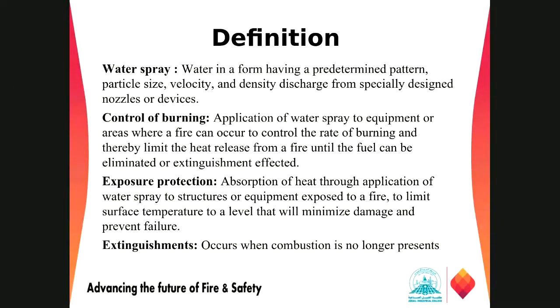Before moving to the topics, we have some definitions associated with this module. What is water spray, right? It is water in a form having a predetermined pattern, particle size, velocity, and density, discharged from specially designed nozzles or devices. Now these nozzles are totally different from the sprinkler system we discussed in NFPA 13.